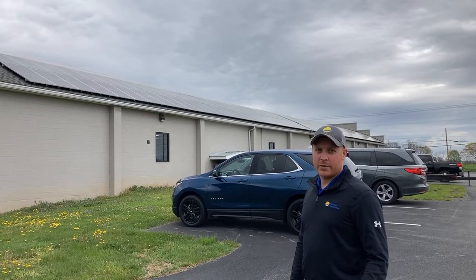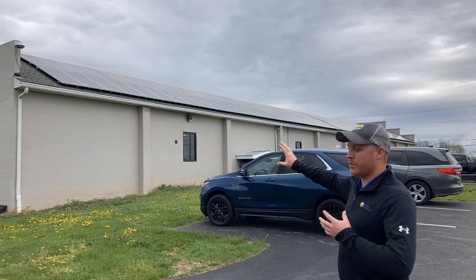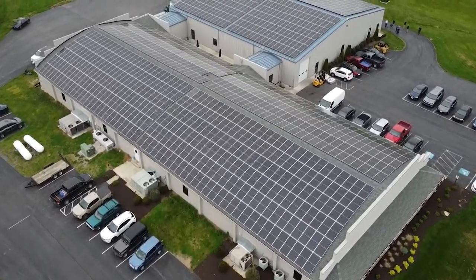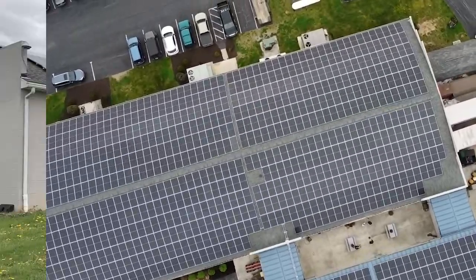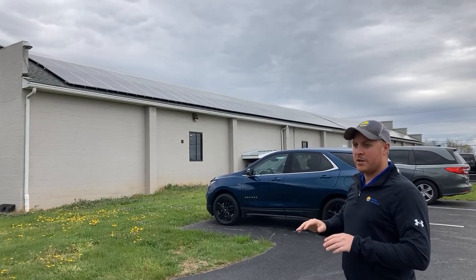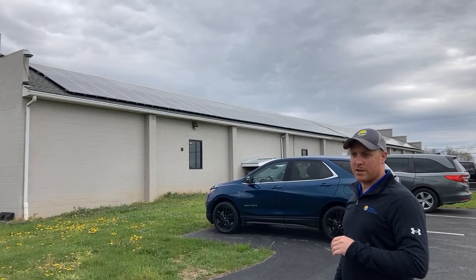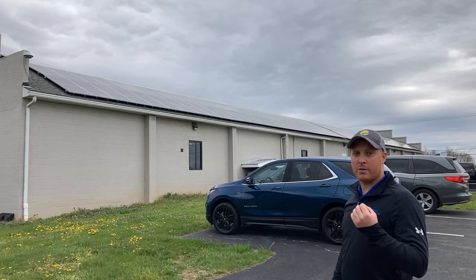The first point we'd highlight would be the rounded roof that's behind me right now. This building is an older building and it has a nice curved roof with curved trusses underneath. So we had to work through the challenge of getting square, flat solar modules to fit on a rounded roof and A, look good, and B, also perform well. We had a lot of engineering support to work through how we were going to attach to the rounded trusses and the purlins in this changing roof.